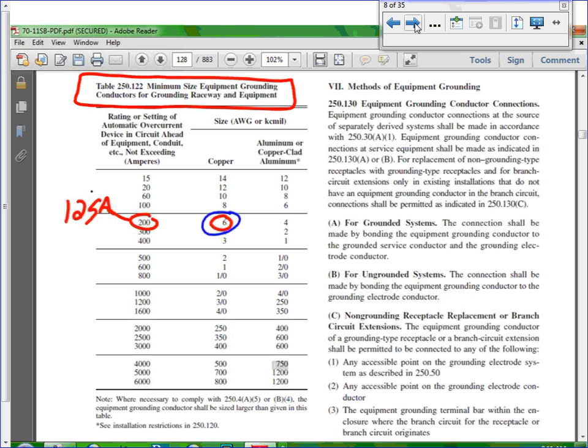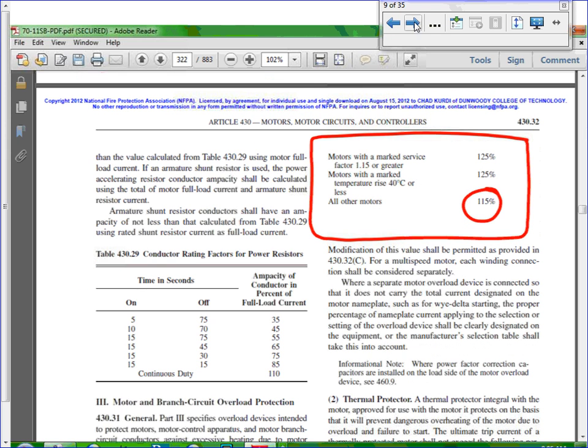Oh, by the way, here's how you find the equipment ground conductor. Here's my 100. Mine was 100 and what did they say? 150. So I'm going to change this one to 150. 150 amp. That will give me the same thing right in here. 200, that will still be number 6. That will still be number 6. Here's where the overload protection is, guys. If you don't know where the overload protection is, I thought these will all be on the network for you so you know where to go. That's where you get the overload protection.